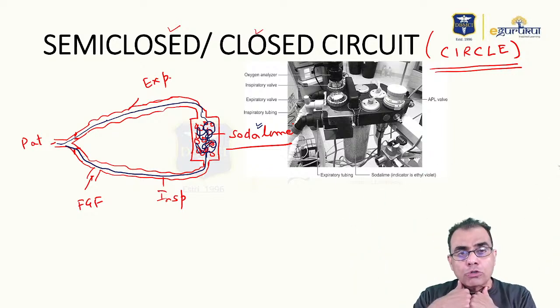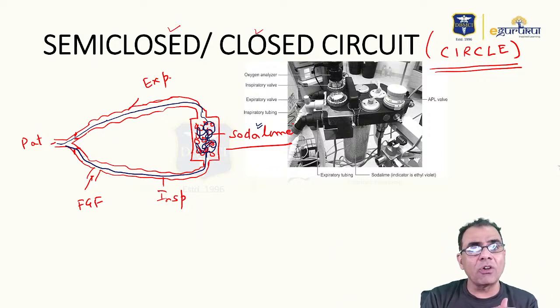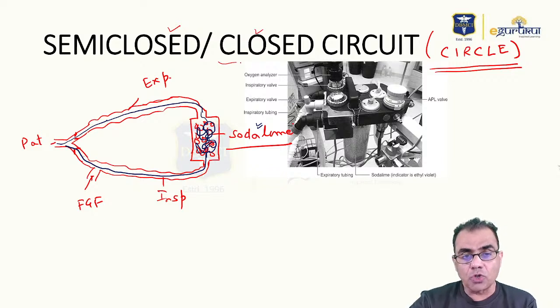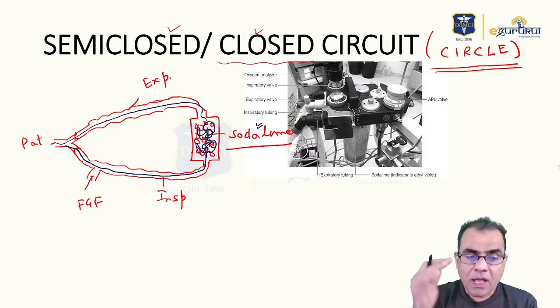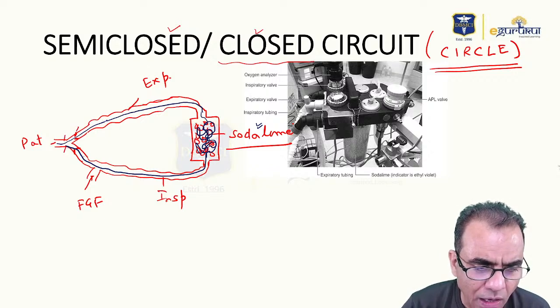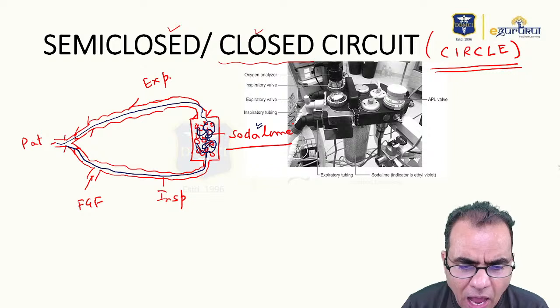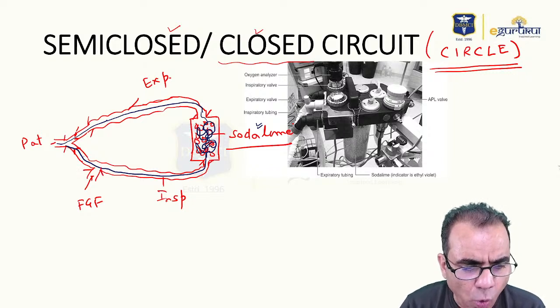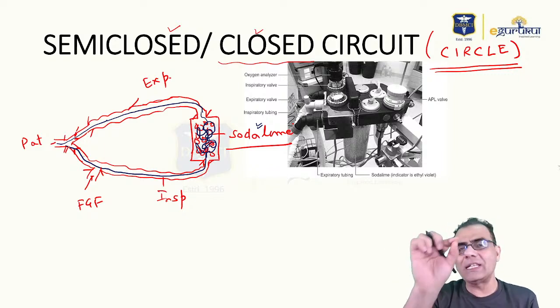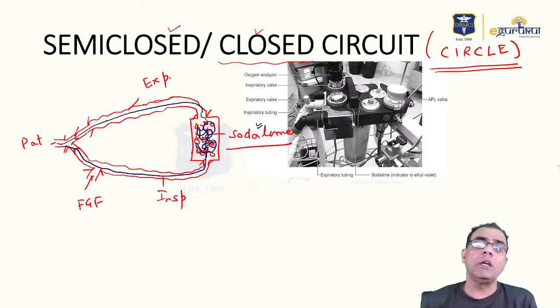Semi-open means that although the majority of gases are venting out into the atmosphere, some are going back into the tubing, which could cause rebreathing. While in a closed circuit, the same gases should be reused after complete absorption of carbon dioxide by soda lime. No gas should vent out into the atmosphere, so this circuit should be closed. But actually this never happens. There are so many points here, here, here, here. There are around 12 or 13 points where there can be leakages. Although the leakages may be minor, they allow some of the gases to vent out into the atmosphere.